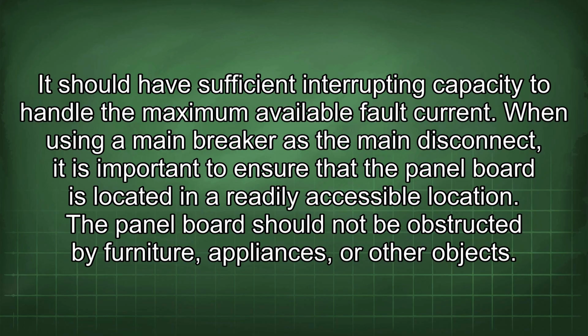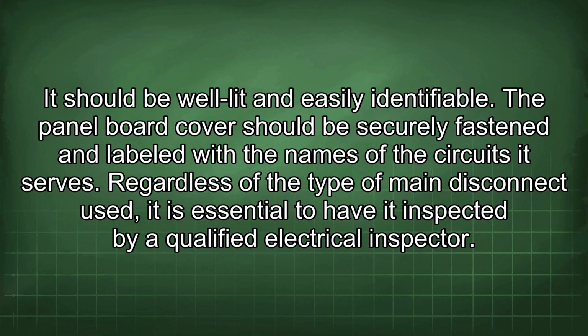When using a main breaker as the main disconnect, it is important to ensure that the panel board is located in a readily accessible location. The panel board should not be obstructed by furniture, appliances, or other objects. It should be well lit and easily identifiable. The panel board cover should be securely fastened and labeled with the names of the circuits it serves.